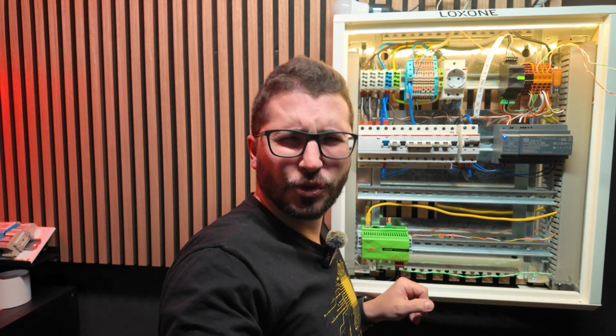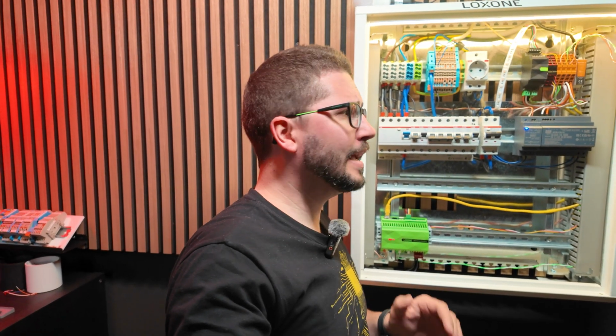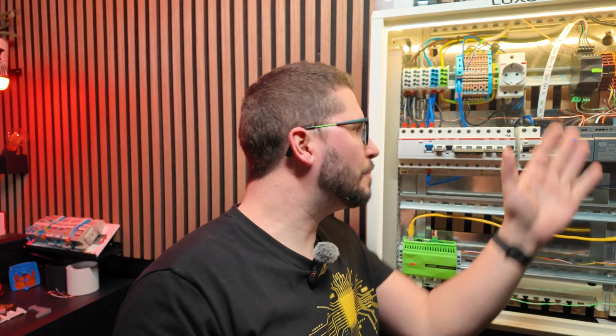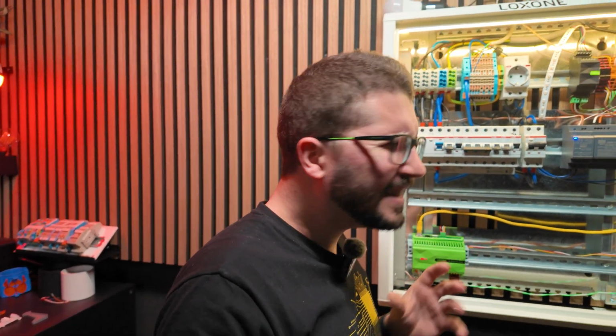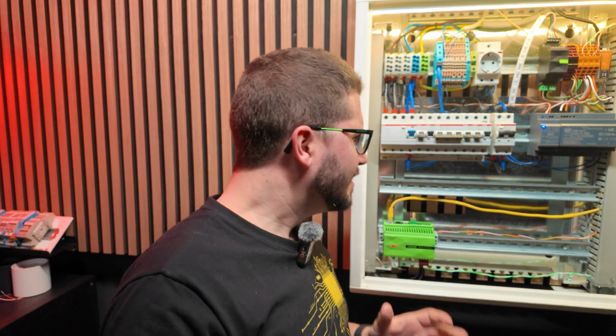But now when we talk about a second or even more power supplies, then comes the greatest mistake in Loxone partners' history, I believe, which is not having the power supplies' grounds connected to one another. Which leads to super, super bad problems. Let's say sometimes when the alarm system is triggering or when all the blinds go up in the whole house, then the system is behaving weirdly. I cannot reproduce it, it's only sometimes. I hope that does not sound familiar to you.